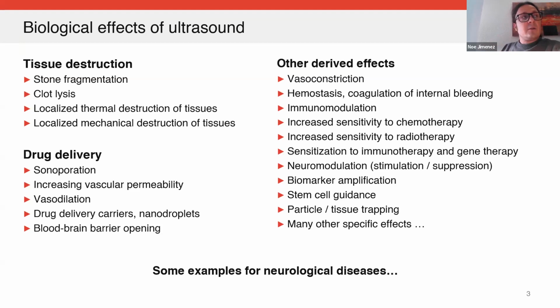And using these thermal effects, you can really raise the temperature until you essentially cook the tissue, but in a very localized way. You can have targets, for example, of 1 millimeter by 1 millimeter by 1 millimeter. This is the typical size of a lesion. It can be even smaller than this, but to have in mind the dimensions of the lesion, this 1 millimeter cube is somehow the limit that you can have using 1 megahertz, which is a normal frequency to interact with the tissues.